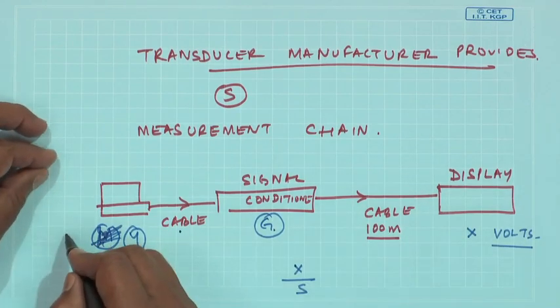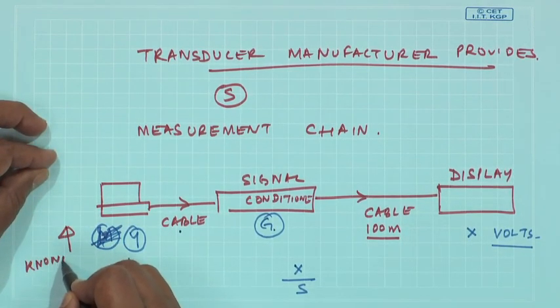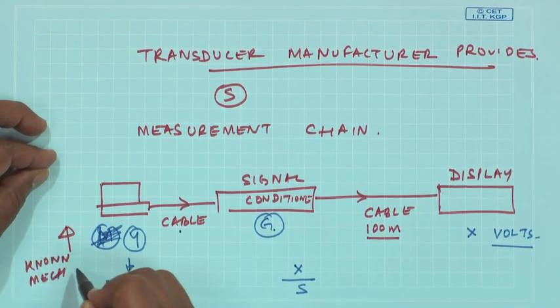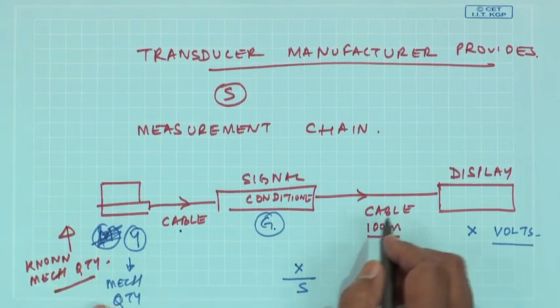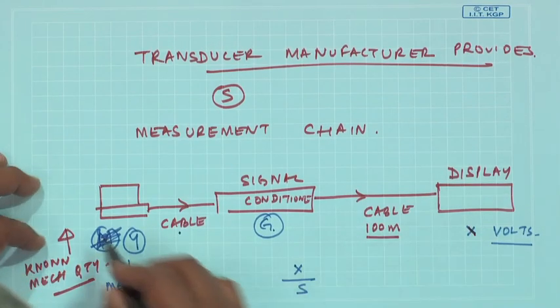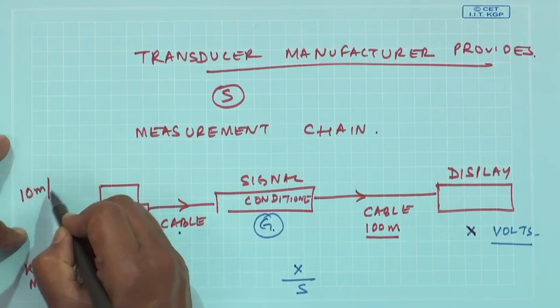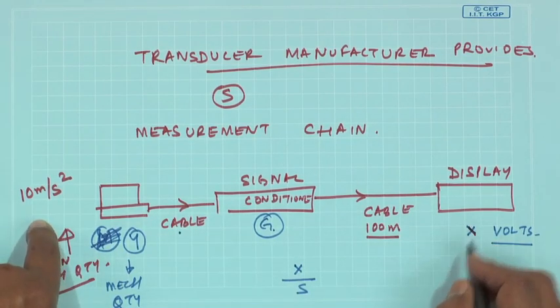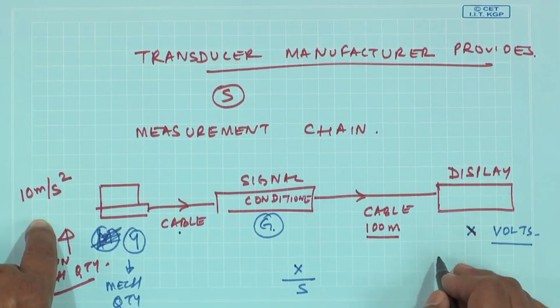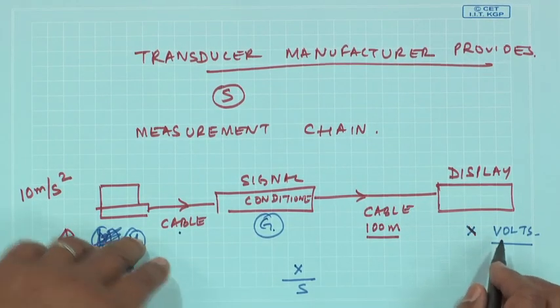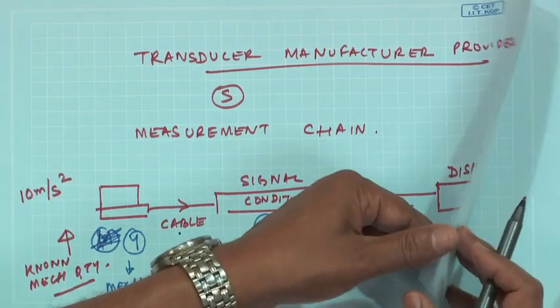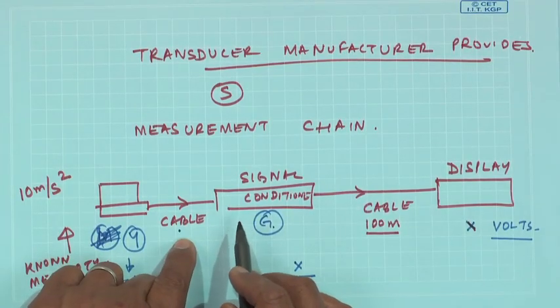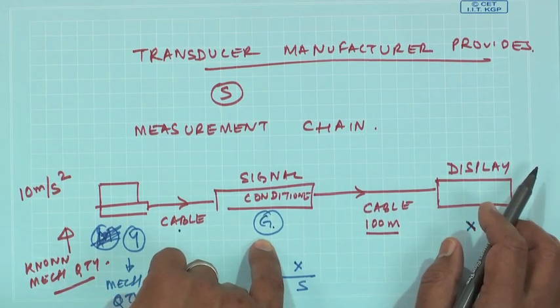Usually in such a scenario, we always give a known mechanical quantity in the field, particularly while you are measuring vibrations. There are calibrators which will give you a known mechanical quantity. If I know I am giving an actual input of 10 meters per second square and I am getting x volts, I know whenever I get y volts it will corresponds to 10 by x times y. This field calibration of transducers is important, because in such a scenario I need not worry about what is the voltage drop in the cable, what is the gain set in the amplifier and so on.